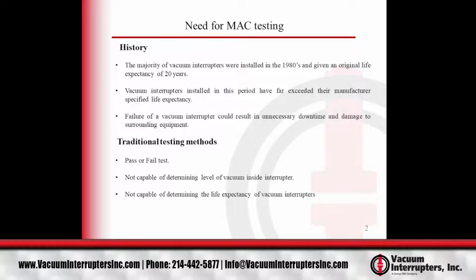The problem with this type of testing is that it doesn't give you any idea of how close to failure you are, so there's no trendable data that goes along with the high pot test. So our MAC tester is able to actually trend this pressure data. The internal pressure of the vacuum interrupter is what provides its insulating ability. So it's able to trend this pressure data over time, and we know approximately when these vacuum interrupters fail. So we can give an estimate of when that failure would occur and give you the opportunity to replace the vacuum interrupter before we reach that point. So next slide, please.